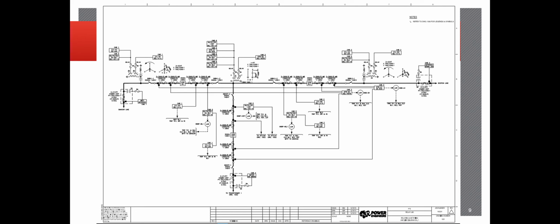So this is a relay one line. You guys have probably seen quite a few of these based on the previous presentations from other groups, but in a sense, what we utilize out in the field is to get a very good understanding for the relay testing purposes, identifying the zones of protection depending on which relays you're going to be testing and where they should end up on the physical one-line layout.